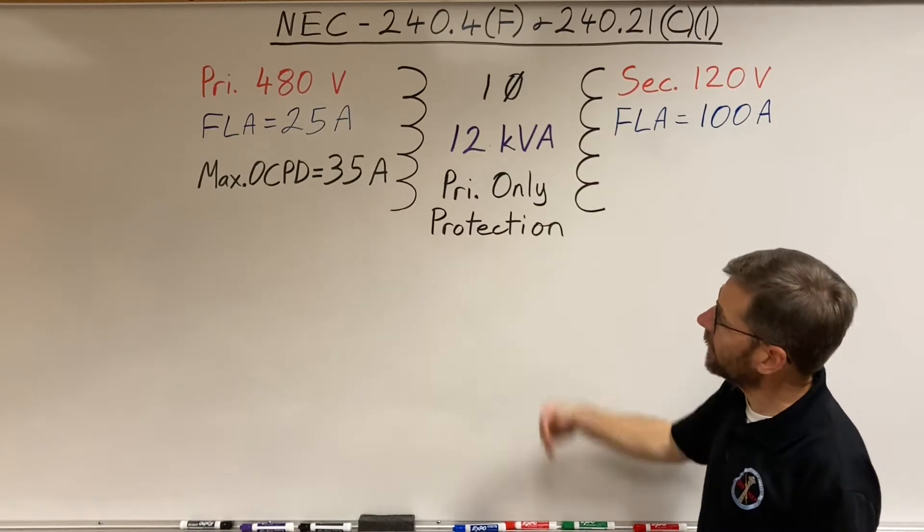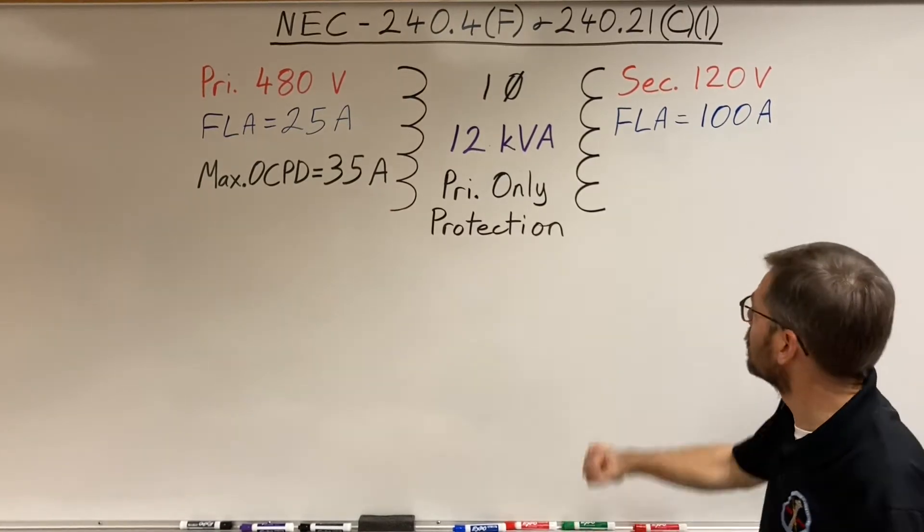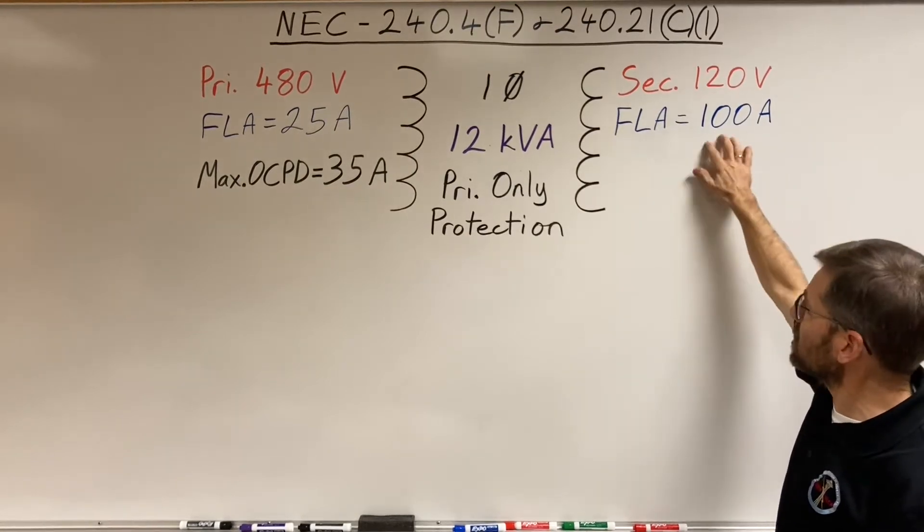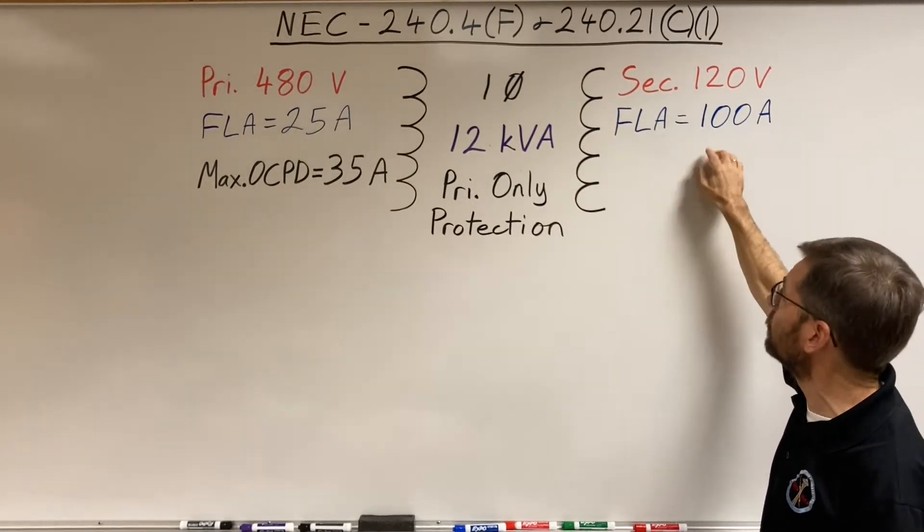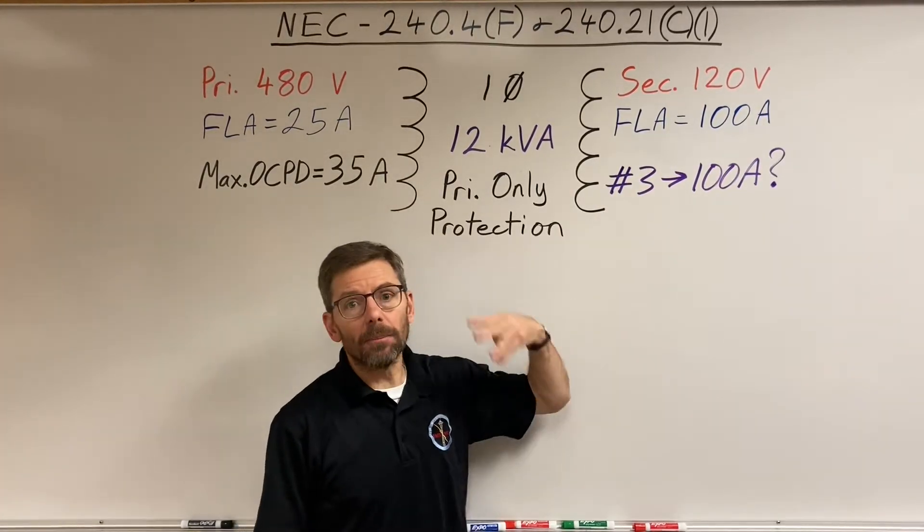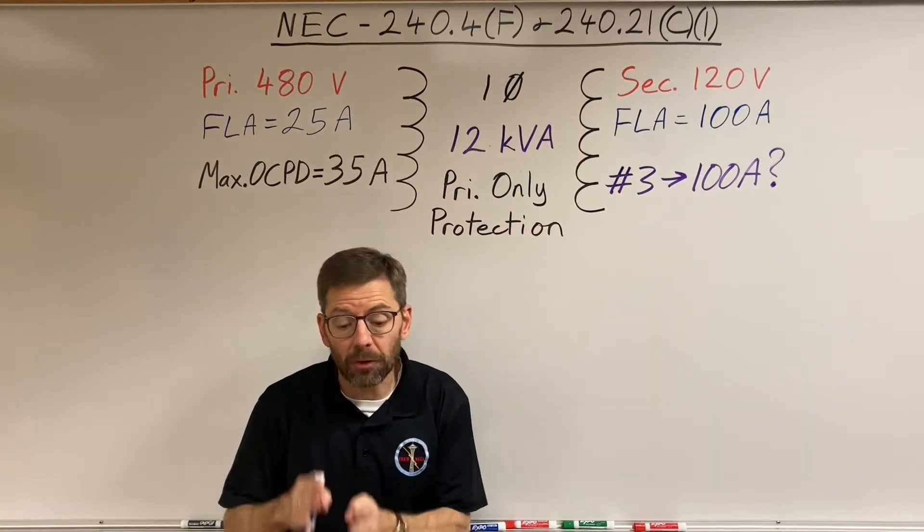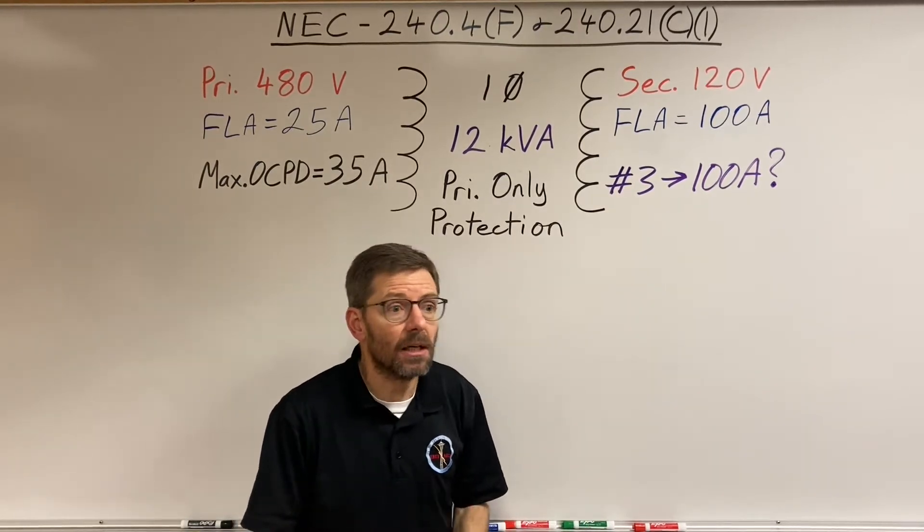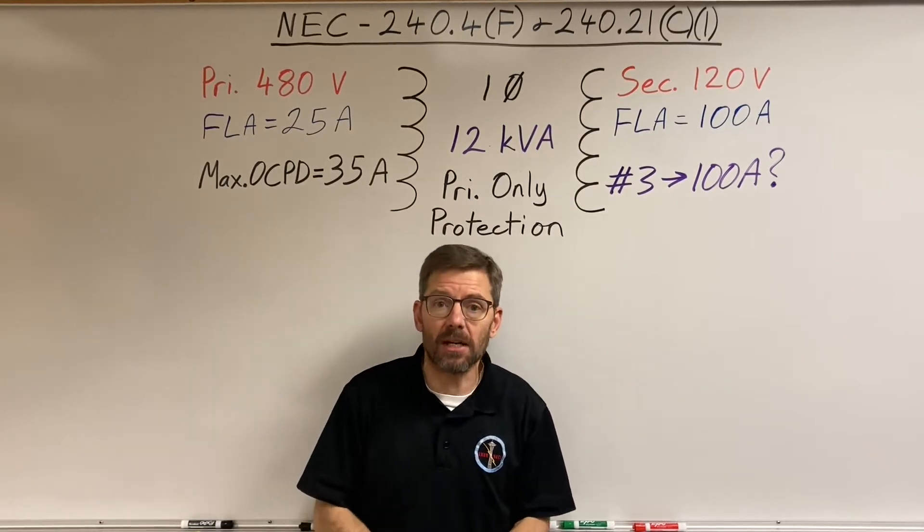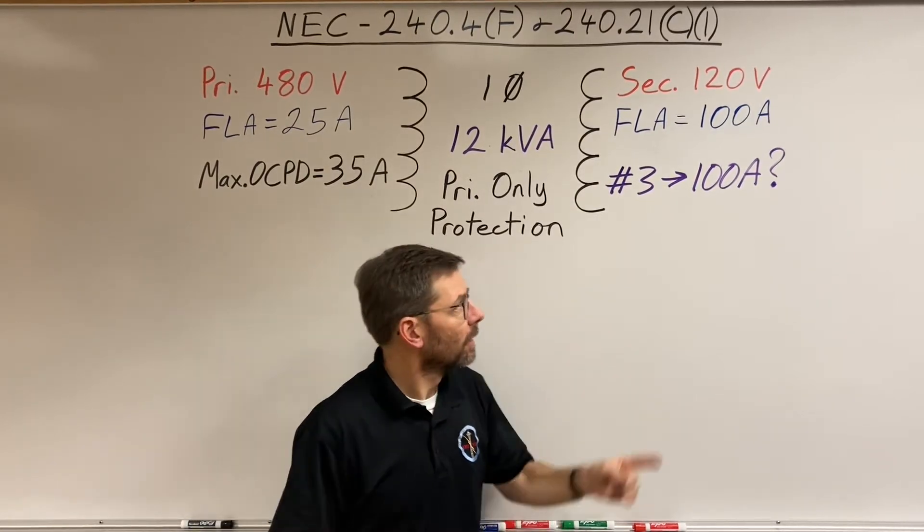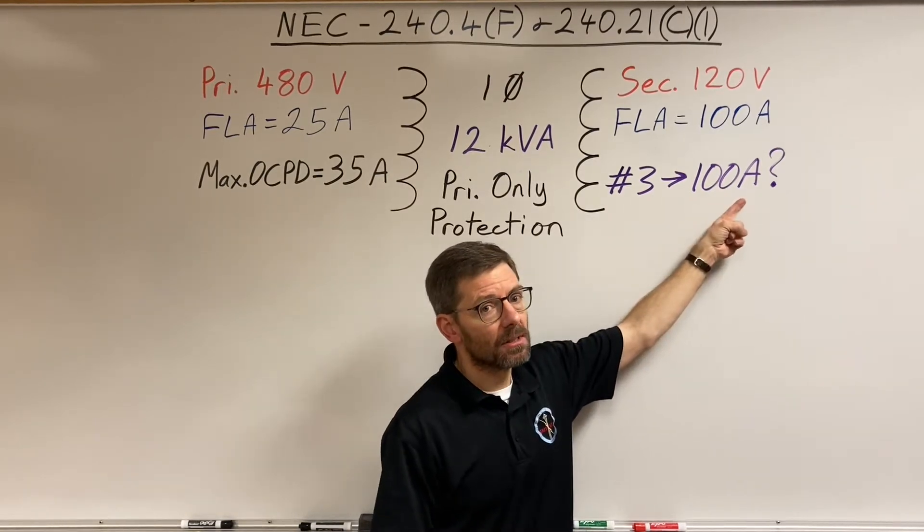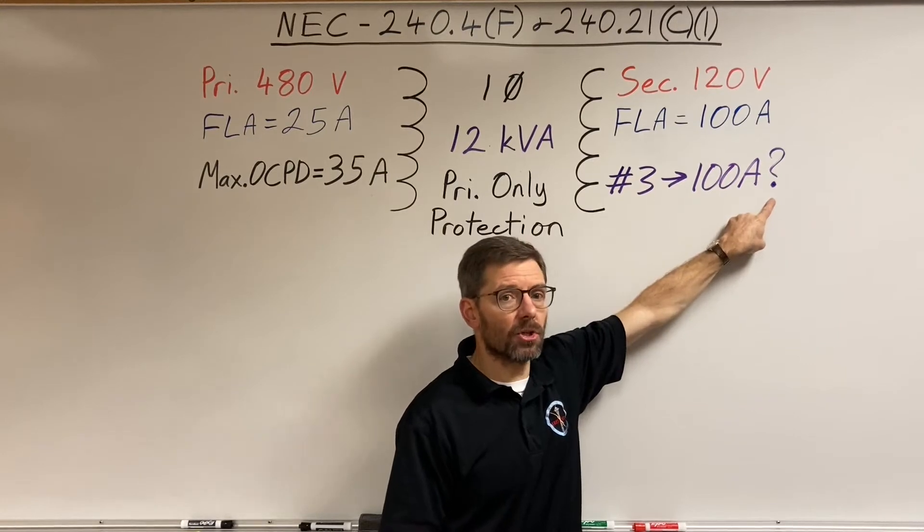Let's see how it calculates out here. We're going to start looking at my secondary full load amps and say, what size conductor do I need minimum to carry 100 amps? I look at my ampacity table 310.16, and I'm looking at 75 degree wire, 75 degree Celsius column copper. I come up with a number three can carry 100 amps. Seems good, but I put a question mark.